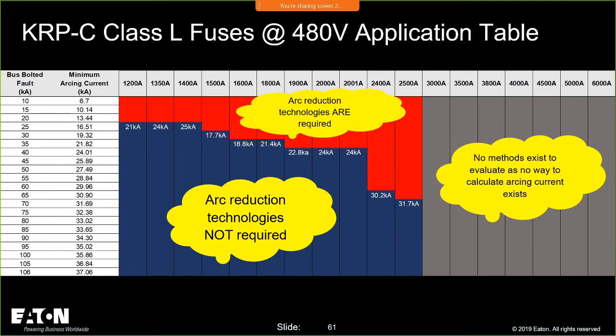I developed this table, which you can see here. I have my bolted fault currents down the left-hand side, and all of my fuse sizes across the top. There is my minimum arcing current coming down the left-hand side of the screen.